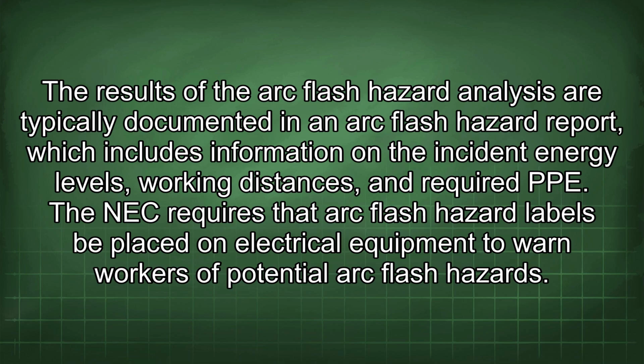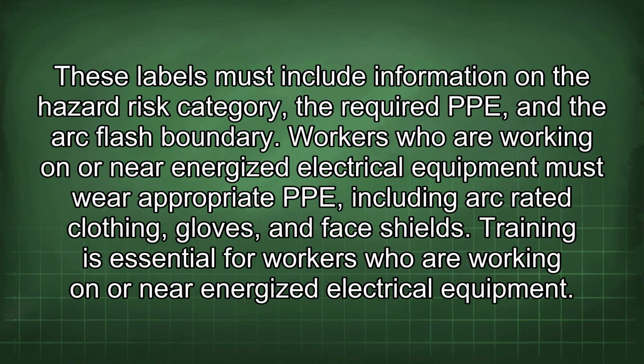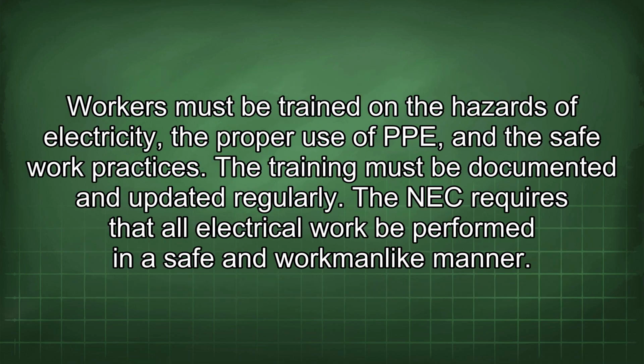The NEC requires that arc flash hazard labels be placed on electrical equipment to warn workers of potential arc flash hazards. These labels must include information on the hazard risk category, the required PPE, and the arc flash boundary. Workers who are working on or near energized electrical equipment must wear appropriate PPE, including arc-rated clothing, gloves, and face shields. Training is essential for workers who are working on or near energized electrical equipment. Workers must be trained on the hazards of electricity, the proper use of PPE, and the safe work practices. The training must be documented and updated regularly.